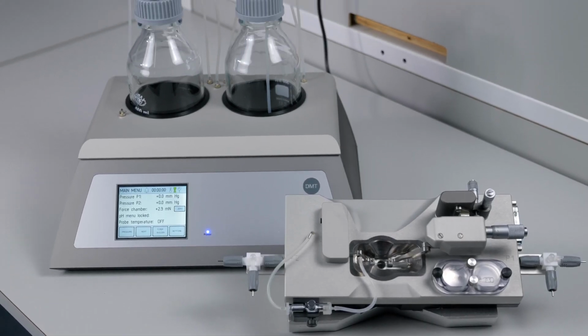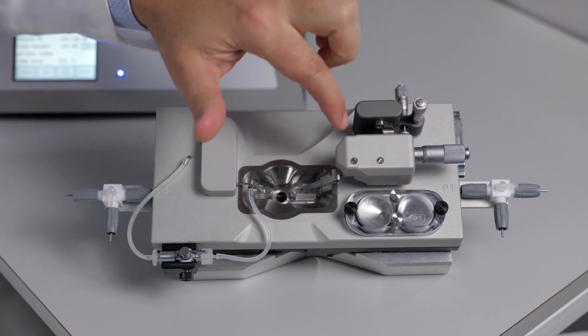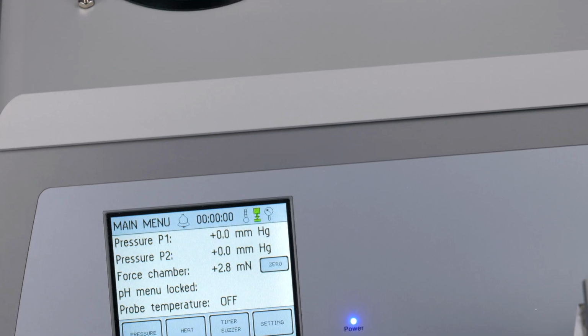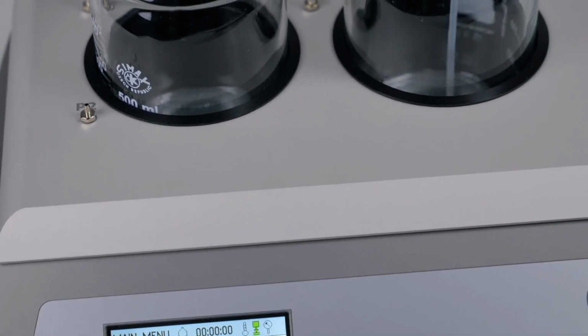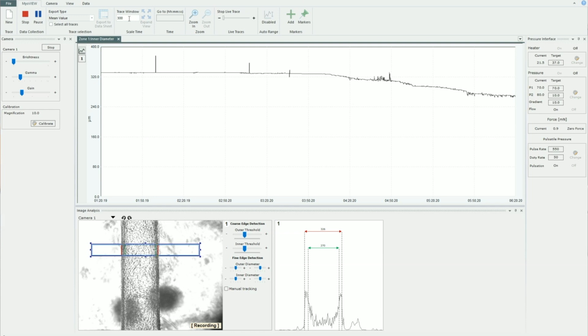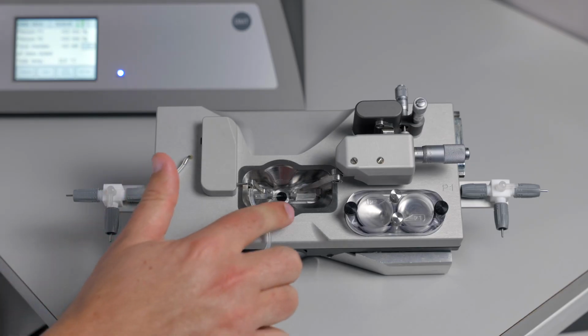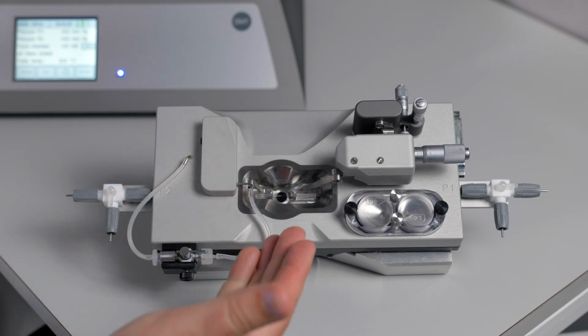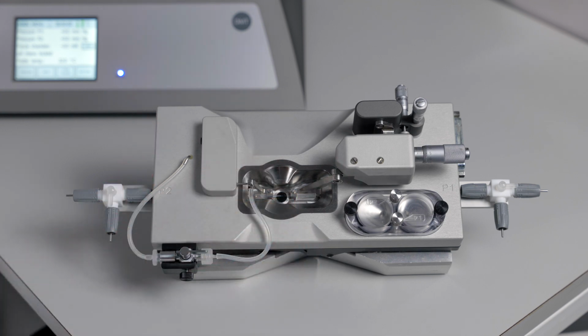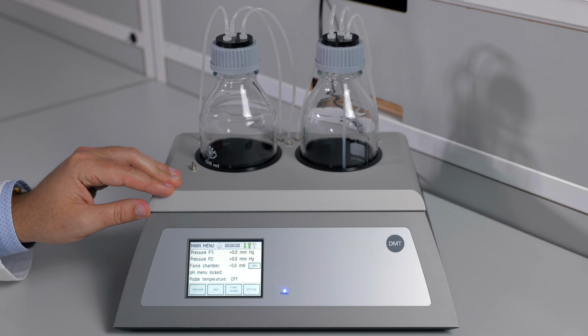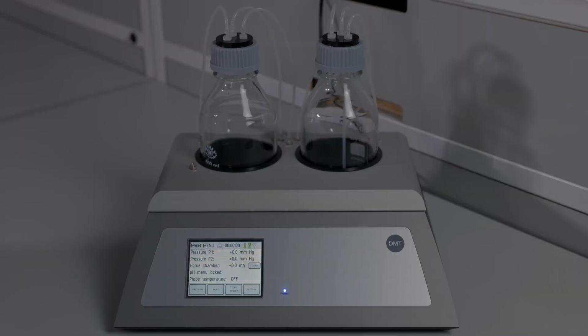The pressure transducers are on either side of the cannulas, so pressure is monitored right before and after your vessel. The MyoVIEW software controls the pressures, the flow rates, and the pulsation settings. It will also automatically track the vessel walls even during 600 beats per minute. The chamber is made from stainless steel, which makes cleaning much easier than plastic or glass chambers where reagents can be difficult to clean away.